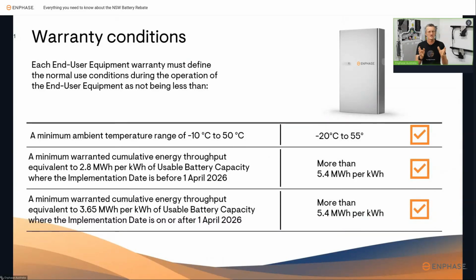What I've tried to do with this slide is show you how the Enphase IQ Battery 5P aligns with this requirement. You can see from the Enphase data sheet, -20 degrees centigrade all the way through to 55 degrees centigrade. So it's a tick for Enphase for that warranty condition requirement. Now, the middle point states a minimum warranted cumulative energy throughput equivalent to 2.8 megawatt hours per kilowatt hour of usable battery capacity.